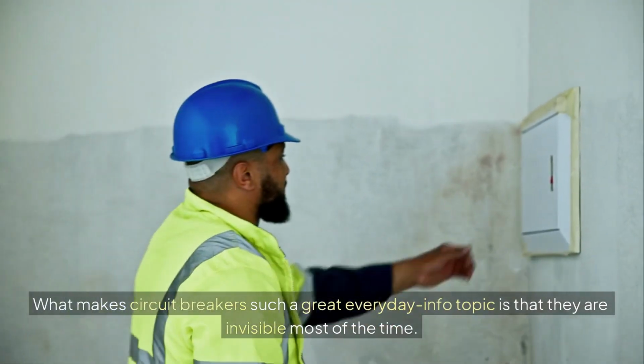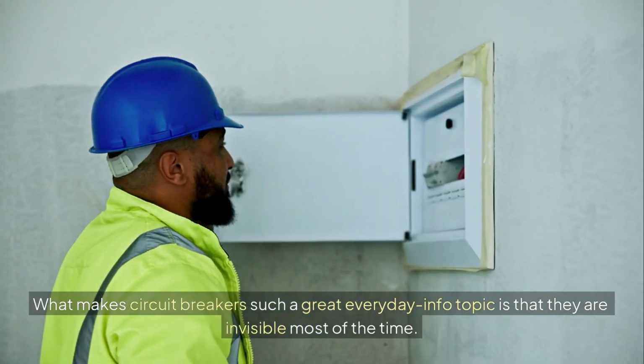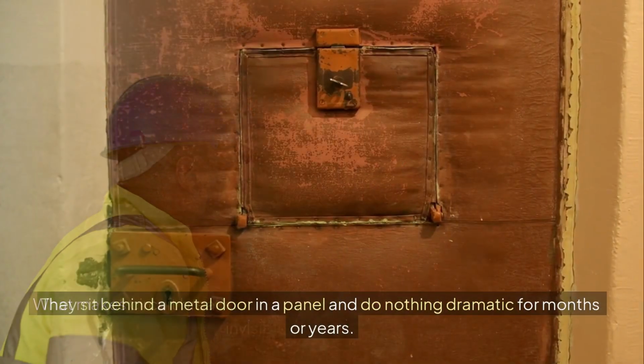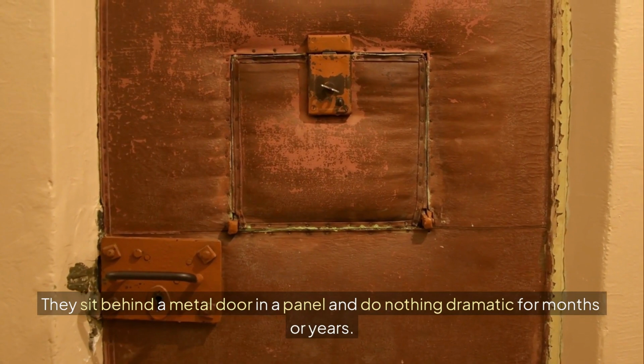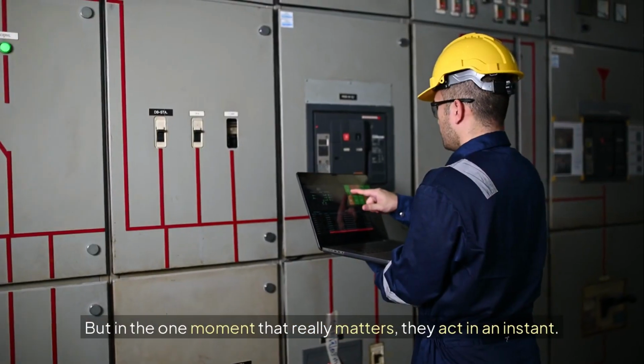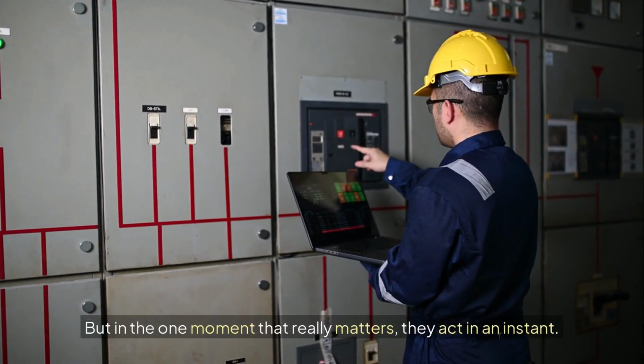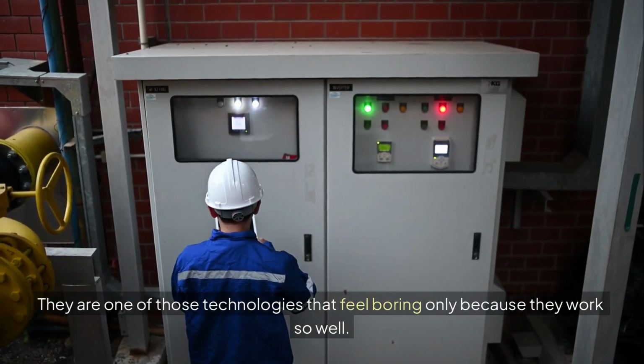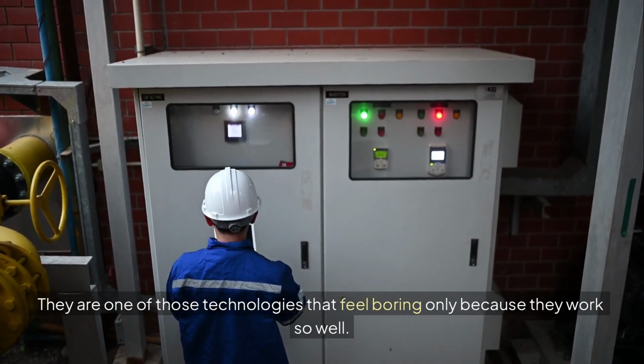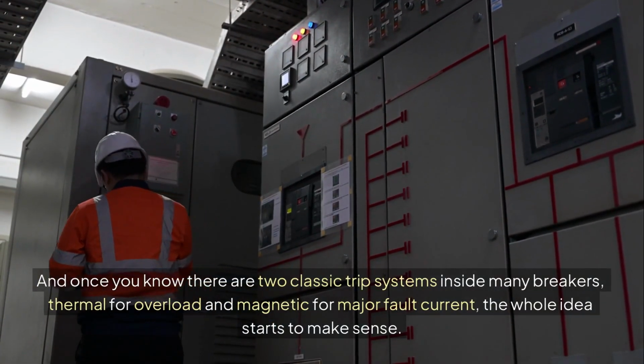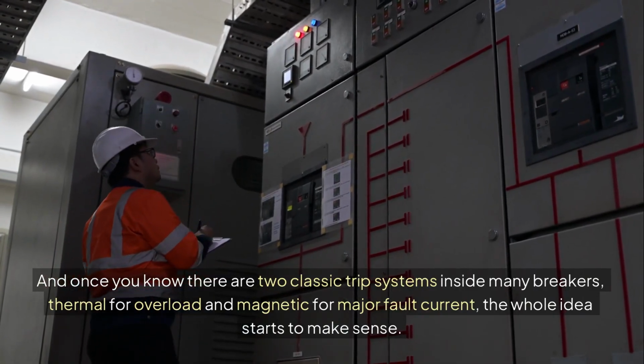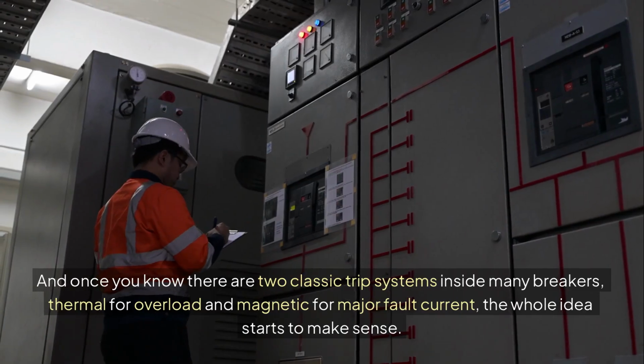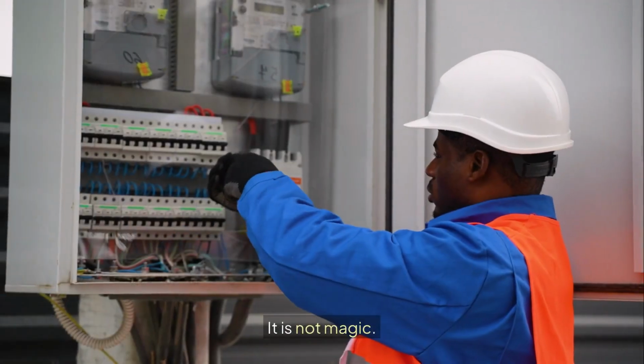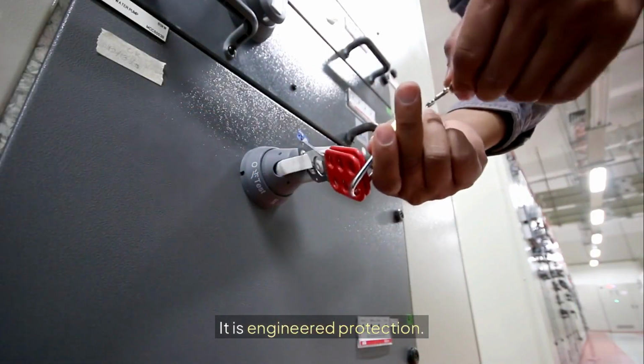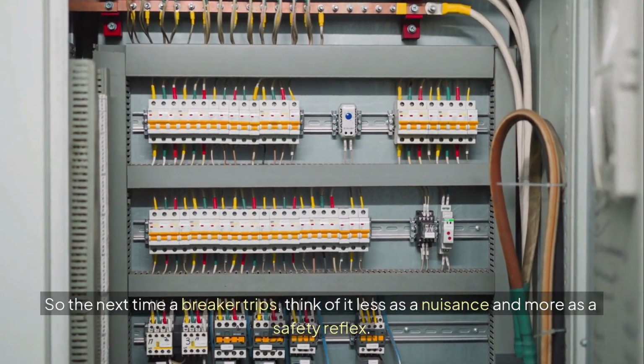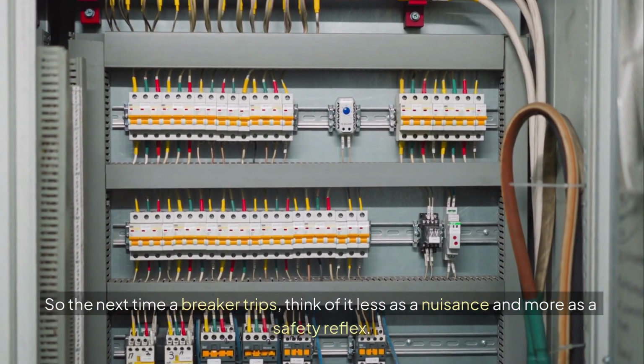Modern relevance. What makes circuit breakers such a great everyday info topic is that they are invisible most of the time. They sit behind a metal door in a panel and do nothing dramatic for months or years. But in the one moment that really matters, they act in an instant. They are one of those technologies that feel boring only because they work so well. And once you know there are two classic trip systems inside many breakers, thermal for overload and magnetic for major fault current, the whole idea starts to make sense. It is not magic. It is engineered protection. So the next time a breaker trips, think of it less as a nuisance and more as a safety reflex.